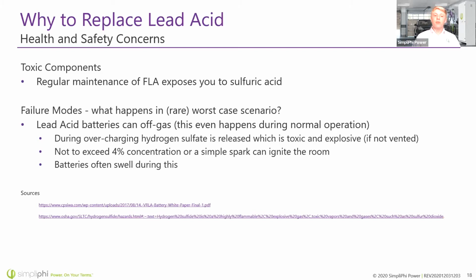As far as failure modes go, the worst case scenario would be a lead acid battery causing an explosion in your home. Lead acid batteries actually off-gas even during normal operation—they produce hydrogen if they're flooded, and hydrogen is not toxic but is explosive. However, if the batteries are overcharged—and this goes for both flooded and AGM or other sealed batteries—they will produce hydrogen sulfide, which is not only toxic but also explosive, and it can ignite with a spark if it's not vented properly.